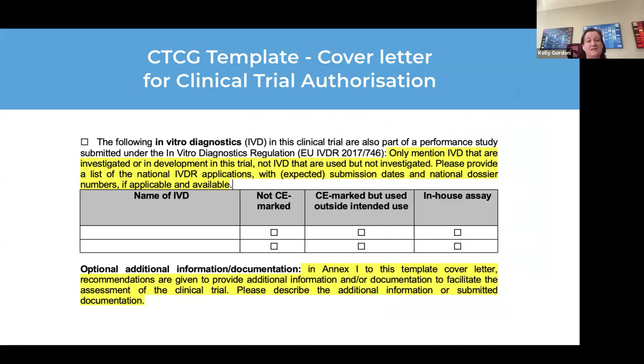Most of the tests that you're working with are not going to be CE marked. You haven't gone through the entire process. So that's why that one doesn't have a star, because it's usually not an option. This would be, for example, if you were using tumor profiling tests that were CE marked, you wouldn't have to comply with these additional regulations. The best way to think of a performance evaluation application is that it's very similar to an investigational device exemption application in the US. It's a lot of documentation that is submitted to the national competent authorities, and I'll give you a list of that type of documentation next.